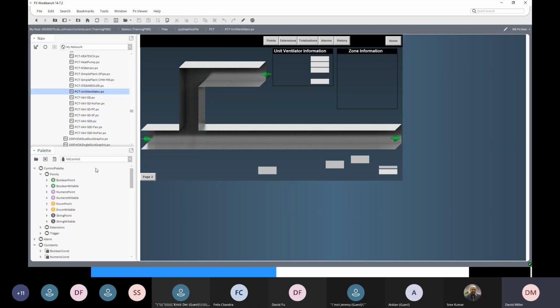To demonstrate a standard graphic, we pretty much would go into CCT, do the system select for, say, central plant chillers with a cooling tower. If we went through that selection, generated a CAF file, and imported that CAF file into our station as a device, then the graphic that we got would match that system selection.